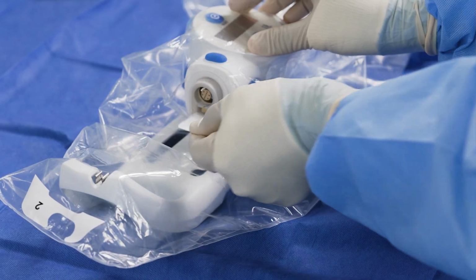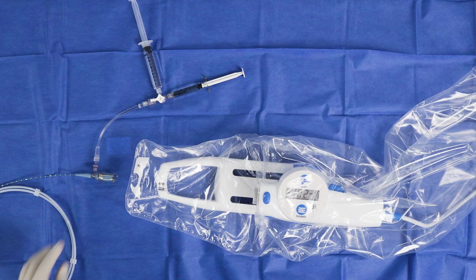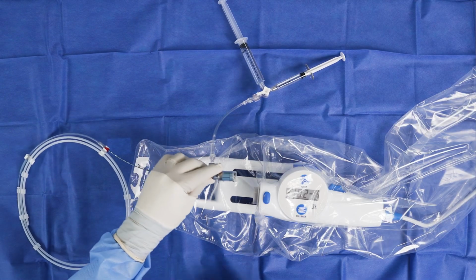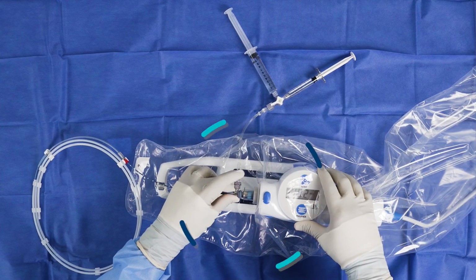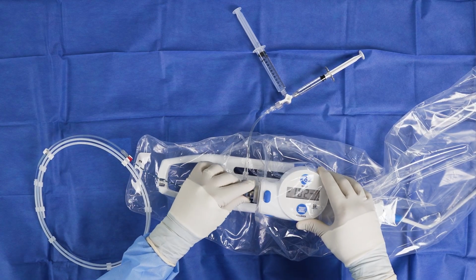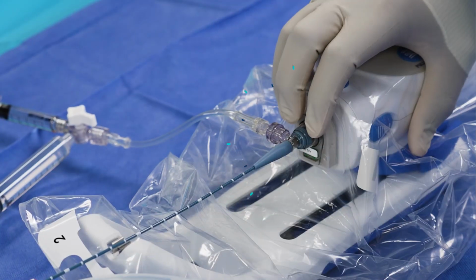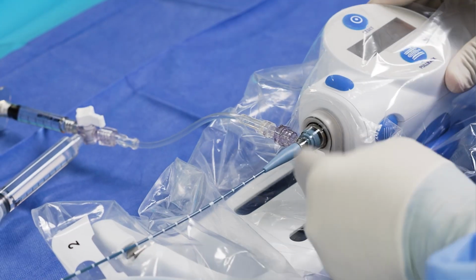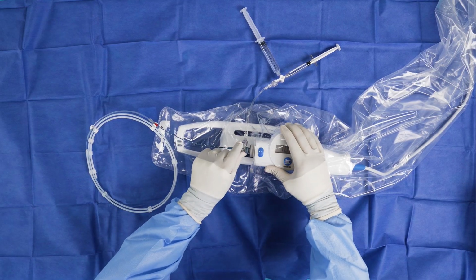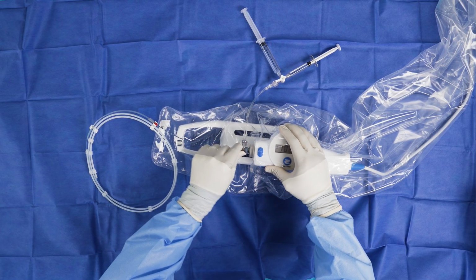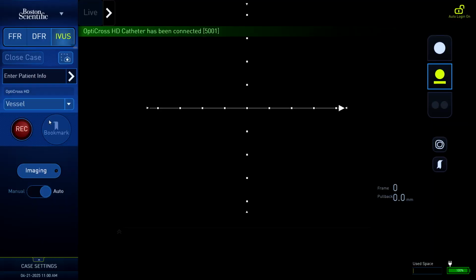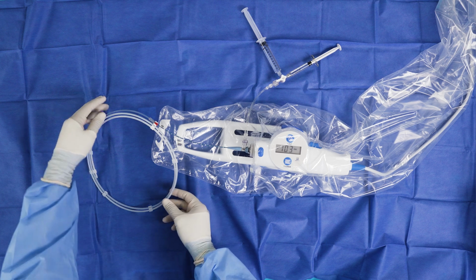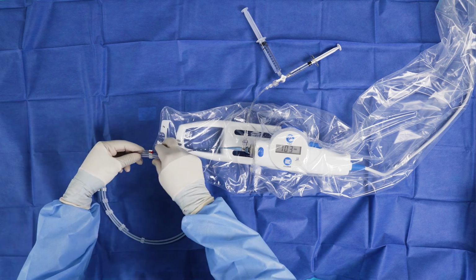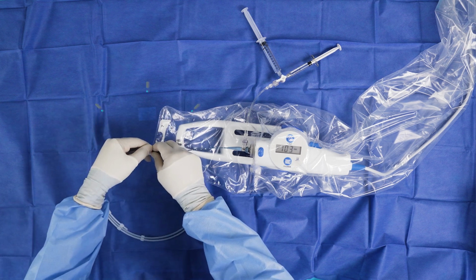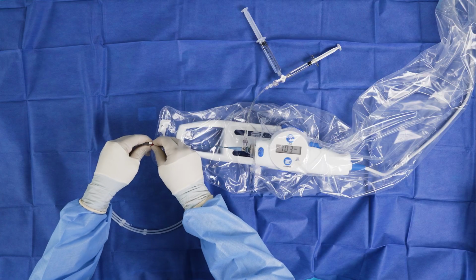Remove the sticker from the catheter connection. Align and connect the catheter hub to the MDU until it clicks into place. Tug on the catheter hub to ensure it is secured with the MDU. Ensure that the system has recognized the correct catheter. Carefully remove the catheter from the sterile hoop dispenser coil.